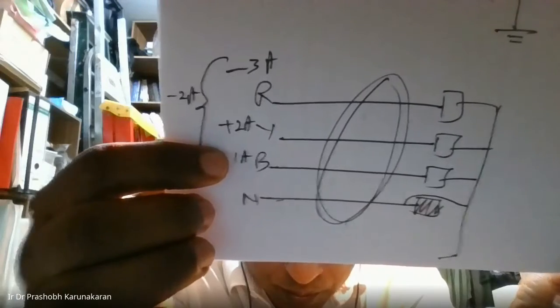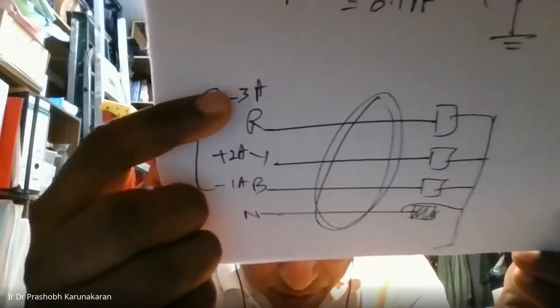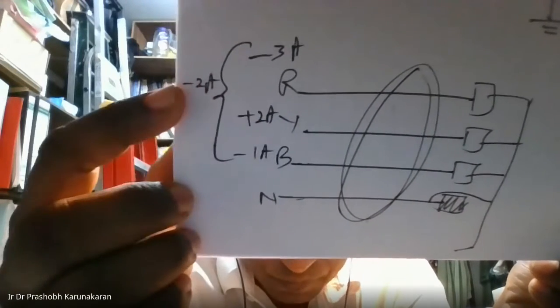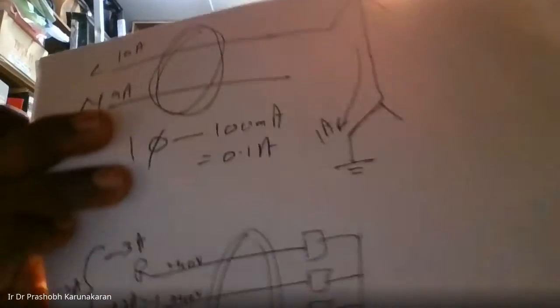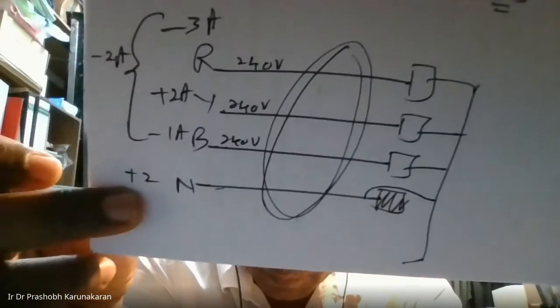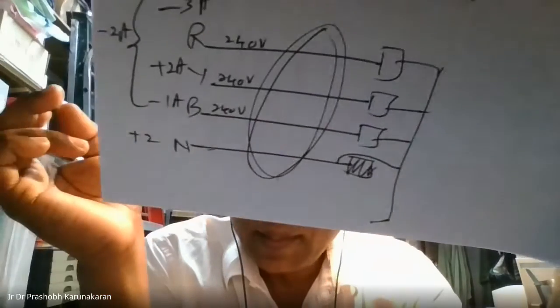So you look at this: -3 minus 1 is -4, plus 2 becomes -2. So the current going in through the three different phases, red, yellow, blue, is -4. Remember that is the amps. The volt is all the same - 240. So if this is -2, automatically this will be +2. So this is how it works - this one total is -2, so this will be +2. So when you put a coil around all four, it's always 0. It can be a coil or it can be a clamp meter. Let me show you the clamp meter.